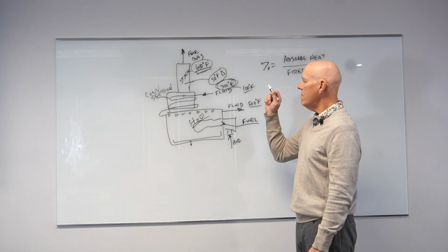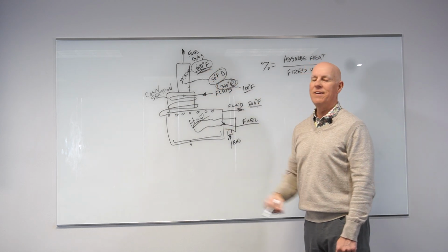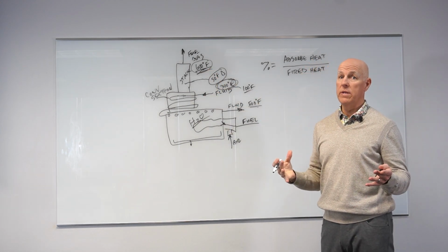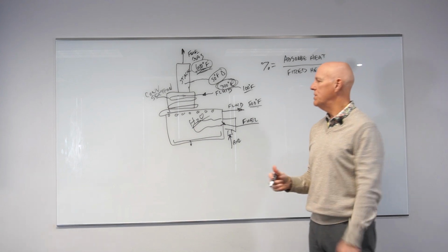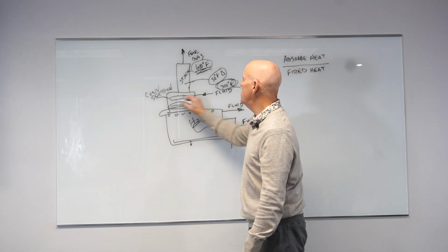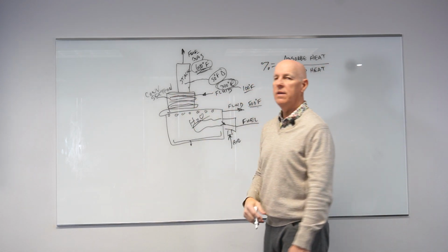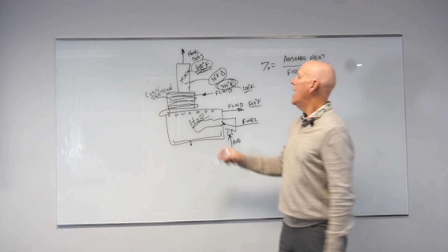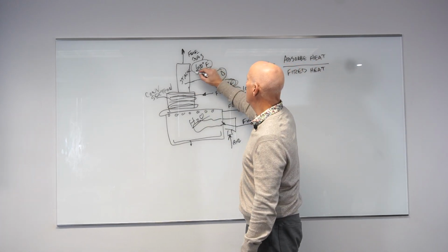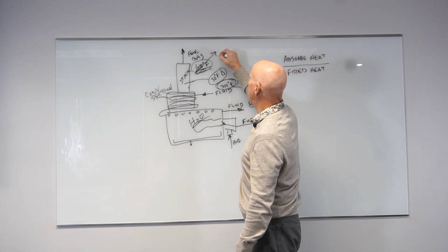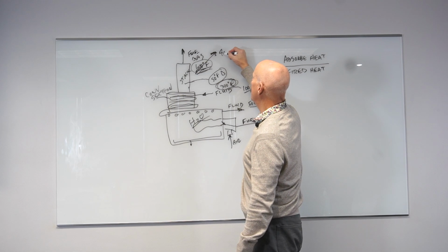So how do I get this down? One way is, hey, let's put more coil in. Let's put more pipe that absorbs the heat. So I could put more tubes in this convection section, more fins, more tubes. Obviously, the more I put in, the lower this goes. It's not unreasonable to get this down to 400 degrees.